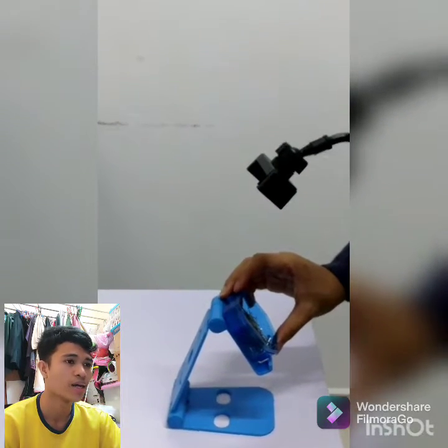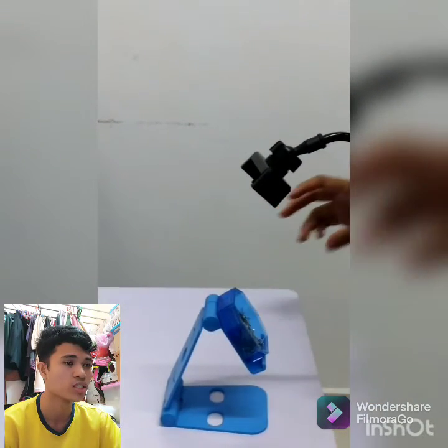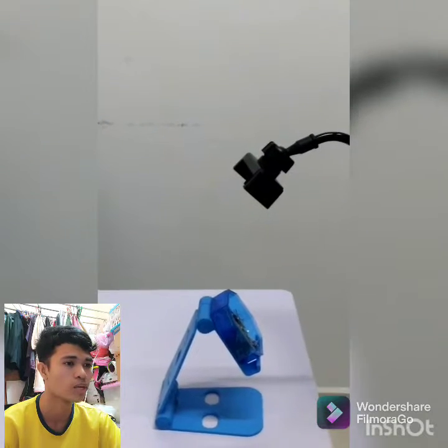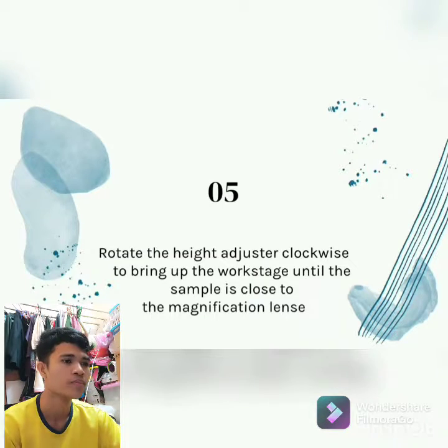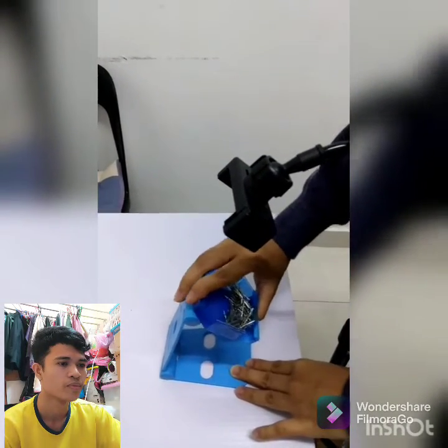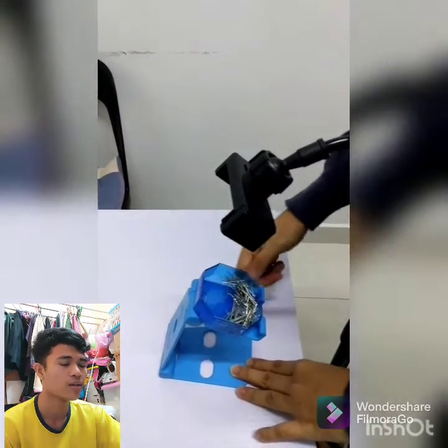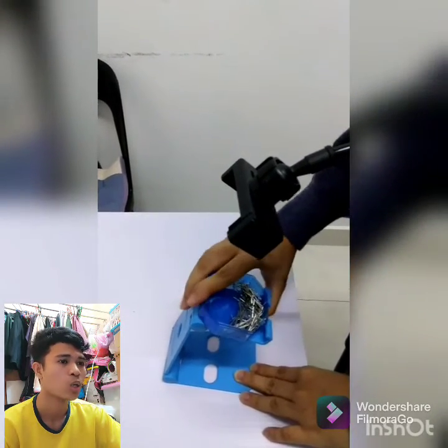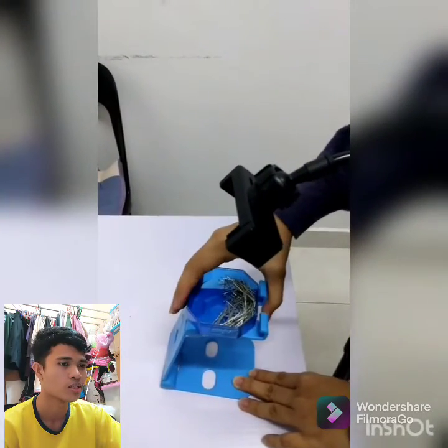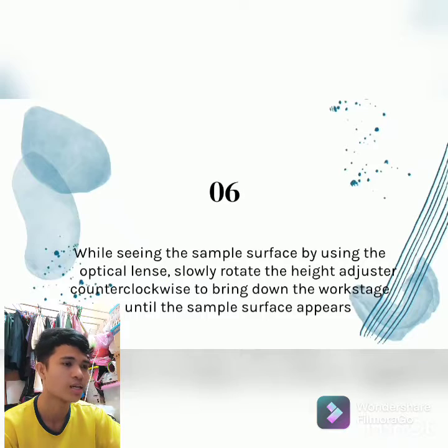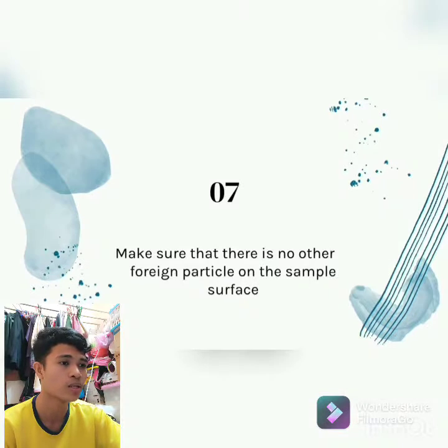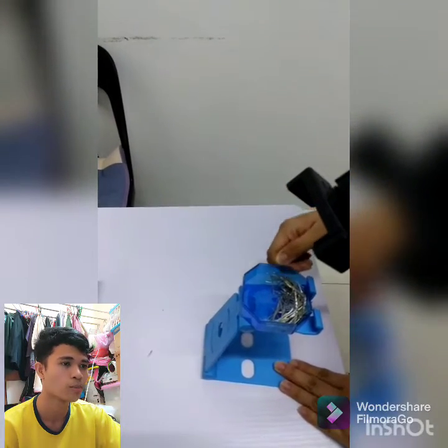Then rotate the height adjuster clockwise to bring up the work stage until the sample is close to the magnification lens. Step 6 is, while seeing the sample surface using the optical lens, slowly rotate the height adjuster counterclockwise to bring down the work stage until the sample surface appears. Then make sure that there is no other fluorescent particle on the sample surface.